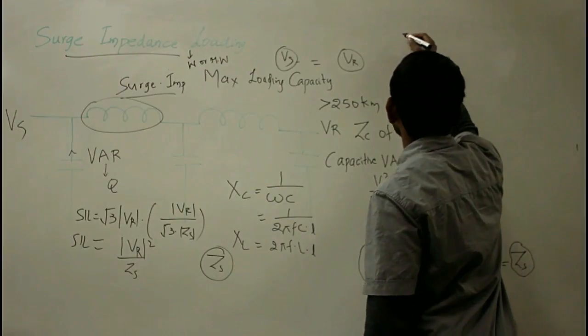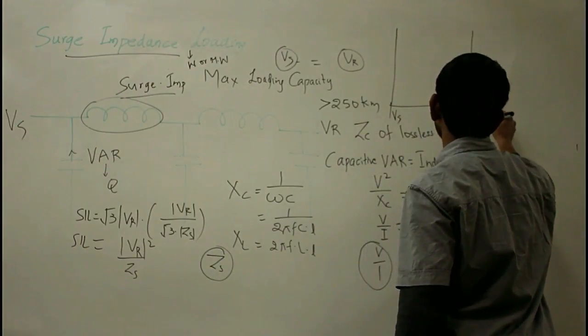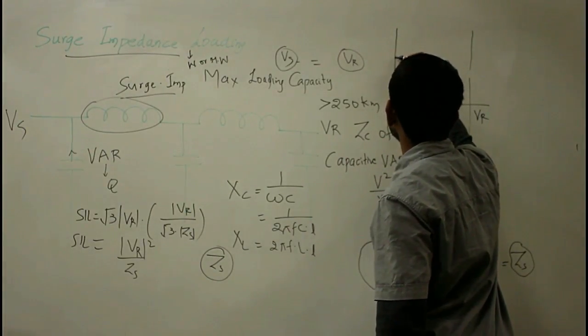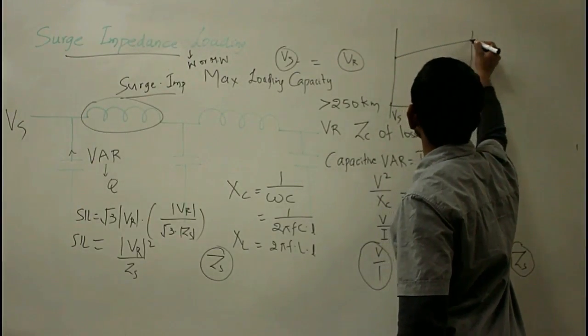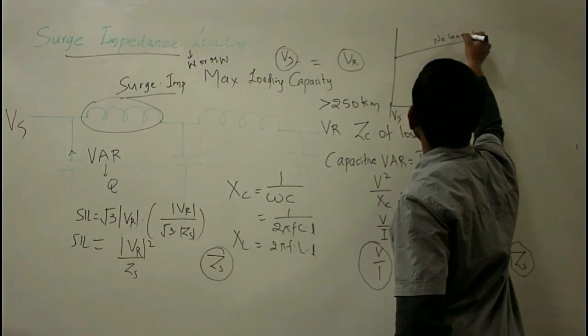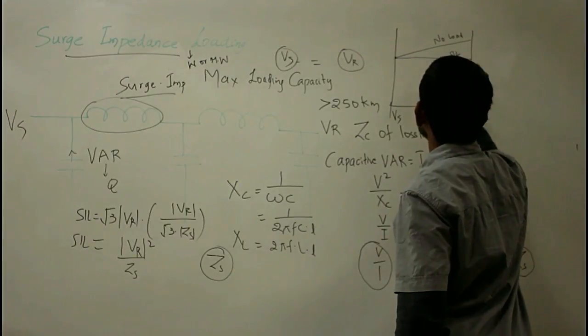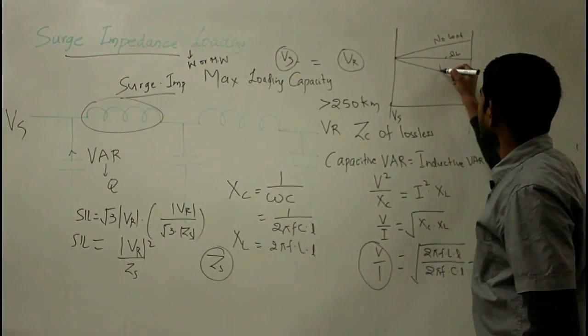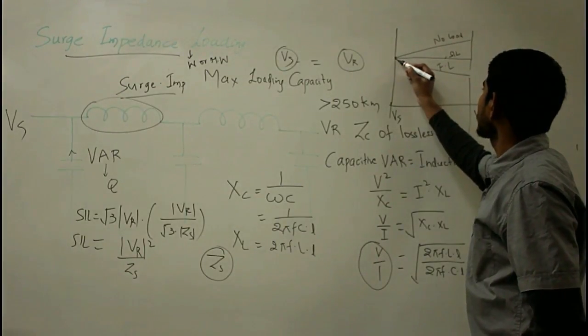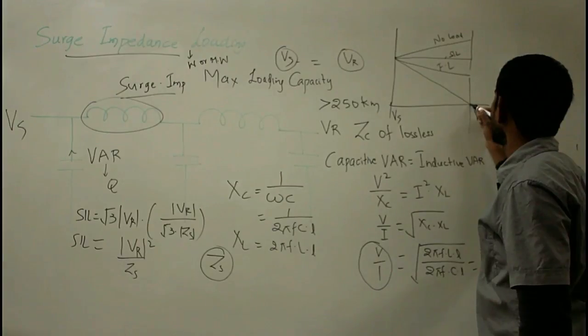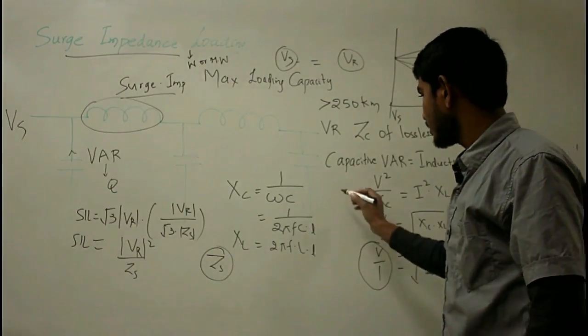Let us plot various voltage profiles for various loadings. For no-load condition, the voltage rises from Vs to VR. The flat voltage profile corresponds to surge impedance loading. For full-load condition, the voltage drops along the line. For short-circuit condition, the voltage drops steeply. The surge impedance ZS — the characteristic impedance of a lossless line — is independent of the length of the transmission line.